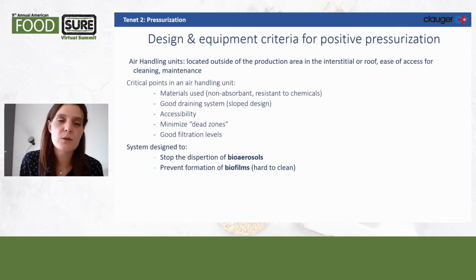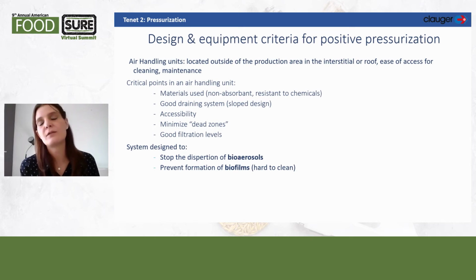So it is important to have air handling units with a good design, because it's often located outside of the production, in the roof or high up. So the material used has to be non-absorbent and resistant to the chemicals for the washing. You have to have a good draining system in order to avoid stagnant water, which could be a source of contamination. You have to have good filtration levels, and generally the system is designed to stop the dispersion of bioaerosol and prevent formation of biofilm, which are hard to clean when they are in the air handling units.